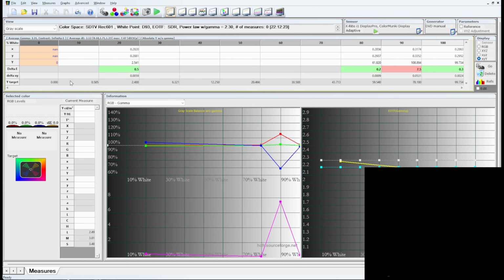And it's going to take 4 or 5 seconds to scan this. And then another pop-up is going to come up. And it's telling me to go to 20. Here we are at 20 IRE, and I'm going to hit OK. Now, go up again. The 30 IRE.